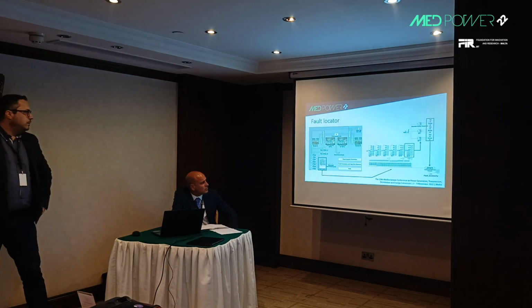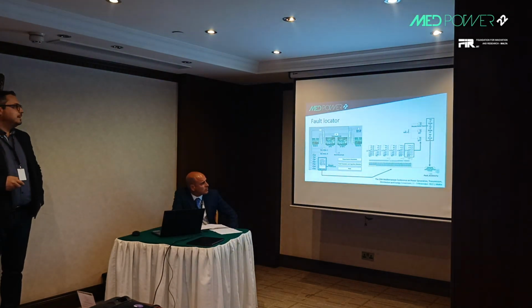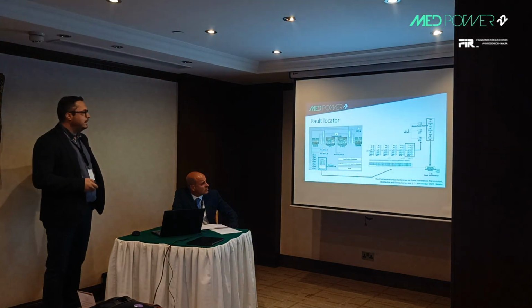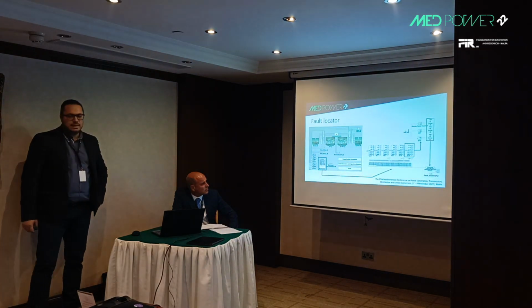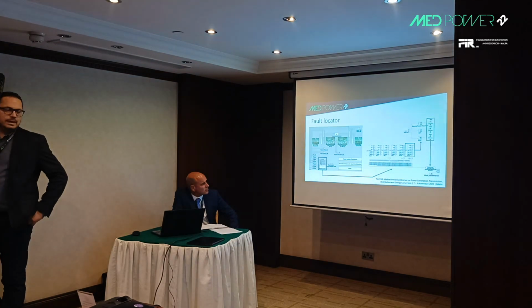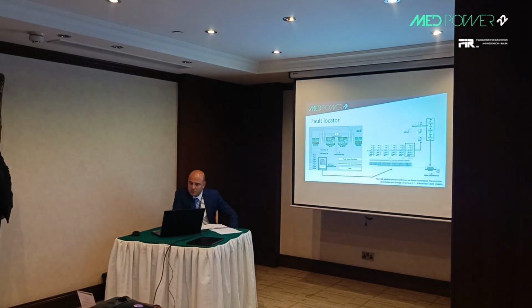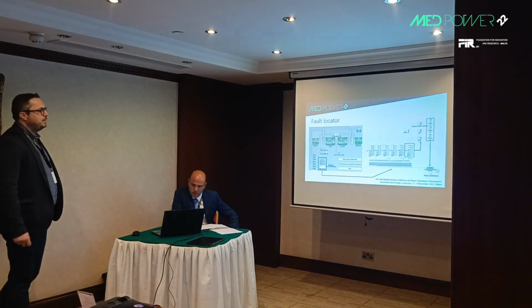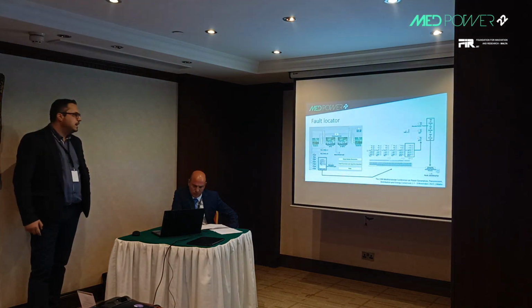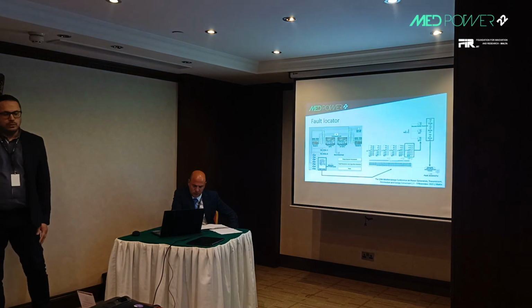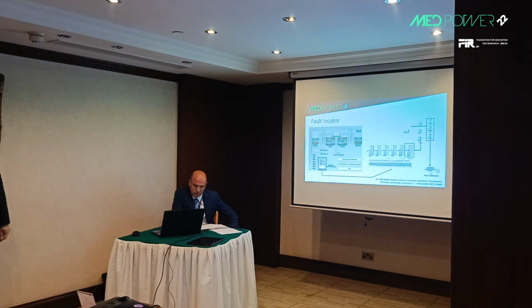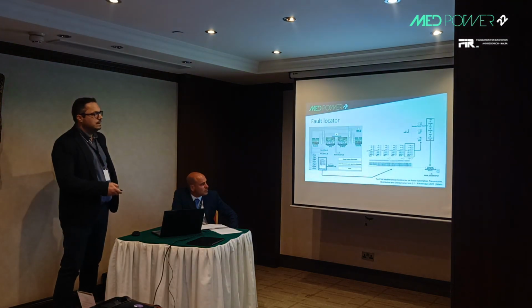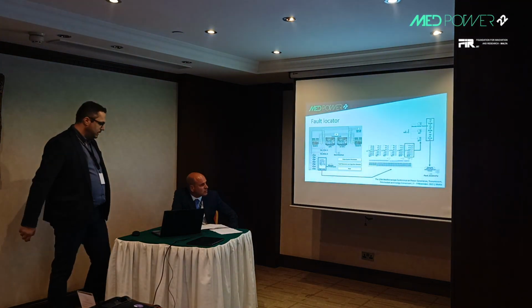The fault locator takes instantaneous voltage and current measurements from both line ends. It includes the signal processing unit, which filters these instantaneous voltage and current measurements and extracts the respective voltage and current phasors. Depending on the fault location algorithm used in the analysis, based on these phasors, the fault distance estimation is calculated.